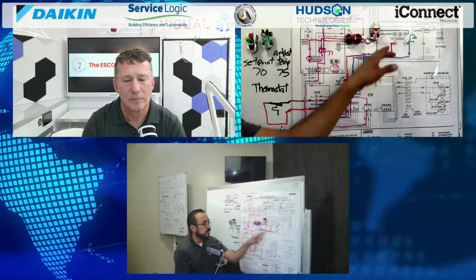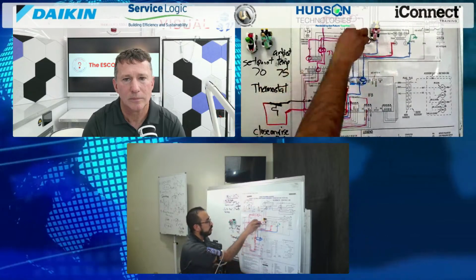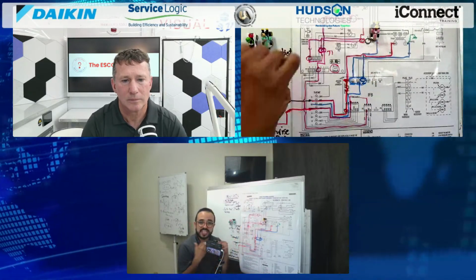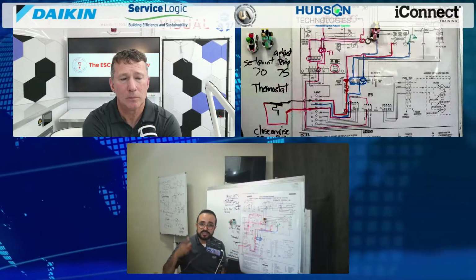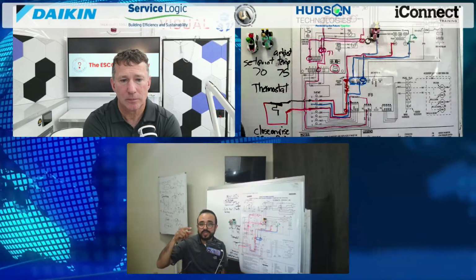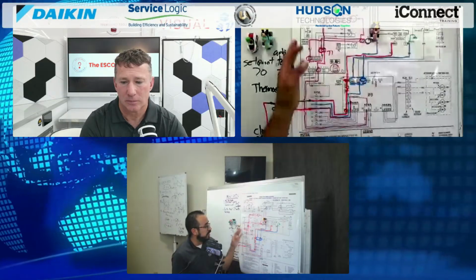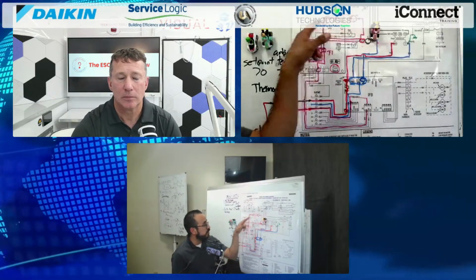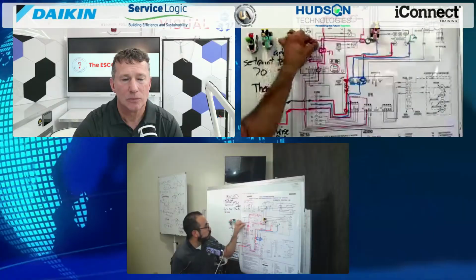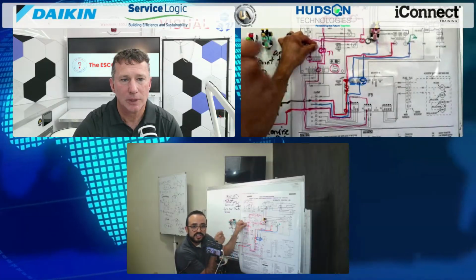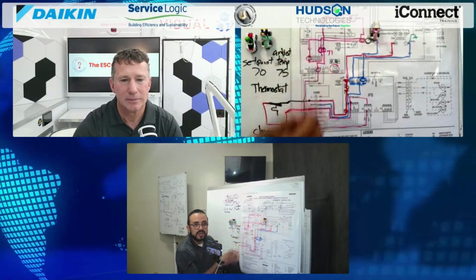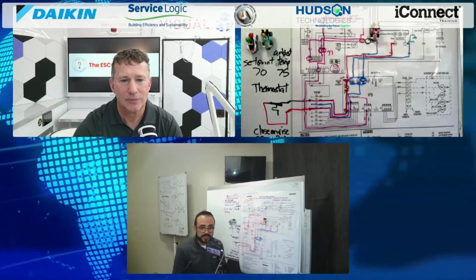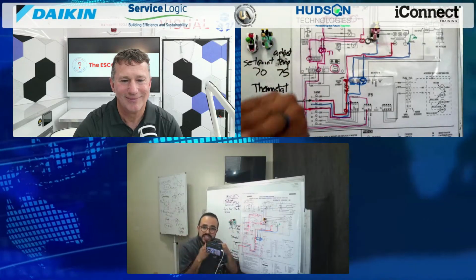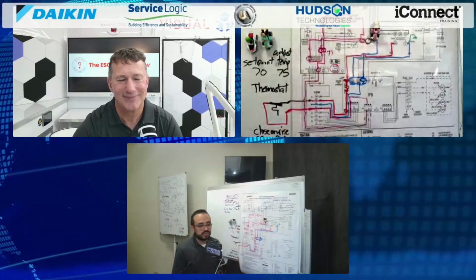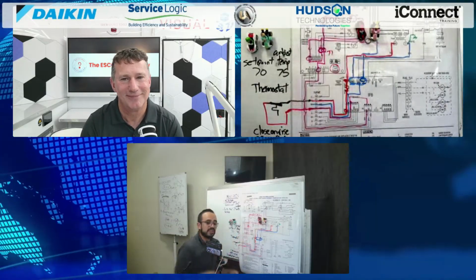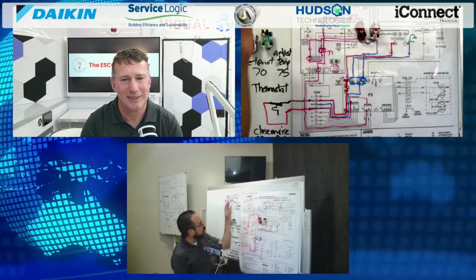So what can you do? A lot of the time the wires don't get taken care of by the pressure switches, they're touching copper or tubing. So what I tell them is unplug everything, unplug the T1 and Y1, go into your pressure switches, unplug it, check one wire to your chassis, to your copper, and if you get continuity, they go to the contactor coil. And boom, that's the concept I teach, going back to the principle.